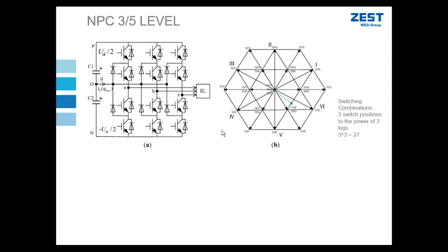Okay, now let's take an example where I want to provide the space vector that is shown in green. That is what my motor is demanding for its specific operating point related to its speed and its voltage. That is represented by the green vector. So that is my desired vector. That is what I want to provide to the motor in terms of my voltage and frequency output. So I've got a number of options. In my low voltage drive, I could only switch a combination of two vectors. Those would be the two vectors closest to the desired vector, and I would switch them in different ratios, different percentages, in order to achieve my desired vector.